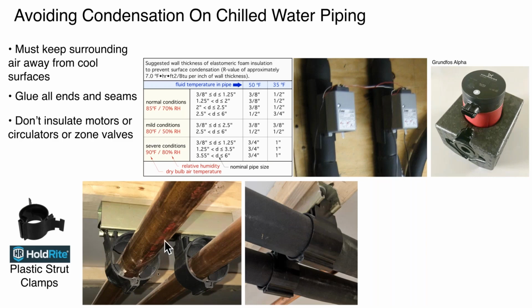This is a clip from HoldRite, and I've used a number of these over the years, and they work very well. It's just a plastic clip that goes into a strut channel. If you look carefully, there are little ribs inside that mechanically support the weight of the pipe, but they also allow the insulation to slide right into both ends of this fixture. It doesn't show it here, but you put a bead of silicone caulk around the outside. And now you've got a nice complete vapor barrier and a properly supported pipe that won't sag over time. There are perhaps other products out there, but we found these to be very useful for this application.